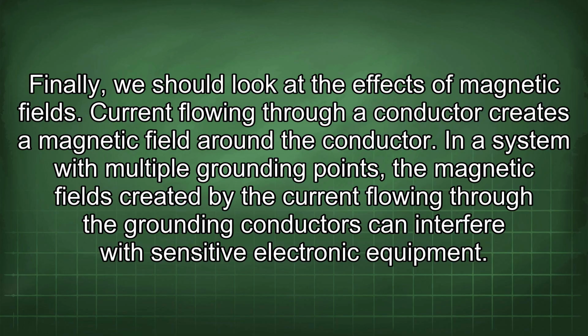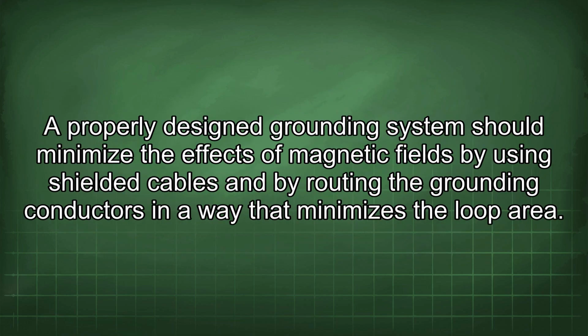Finally, we should look at the effects of magnetic fields. Current flowing through a conductor creates a magnetic field around the conductor. In a system with multiple grounding points, the magnetic fields created by the current flowing through the grounding conductors can interfere with sensitive electronic equipment. A properly designed grounding system should minimize the effects of magnetic fields by using shielded cables and by routing the grounding conductors in a way that minimizes the loop area.